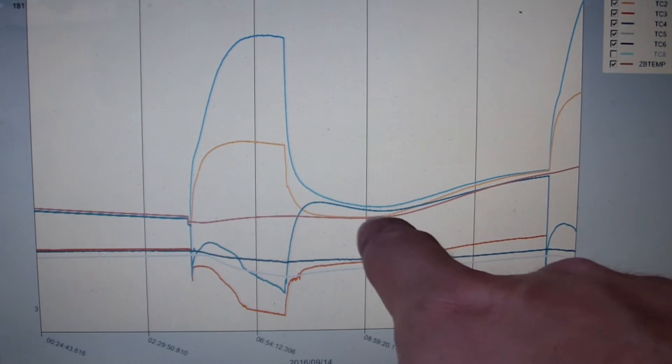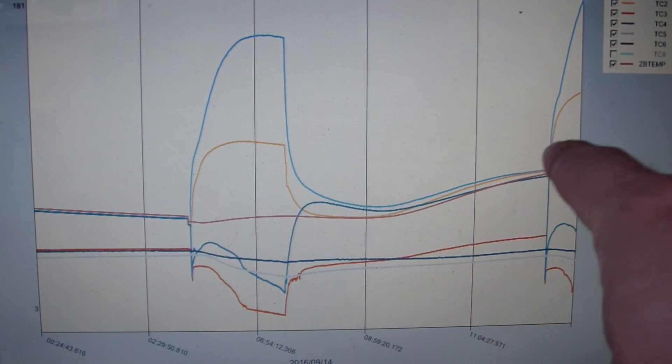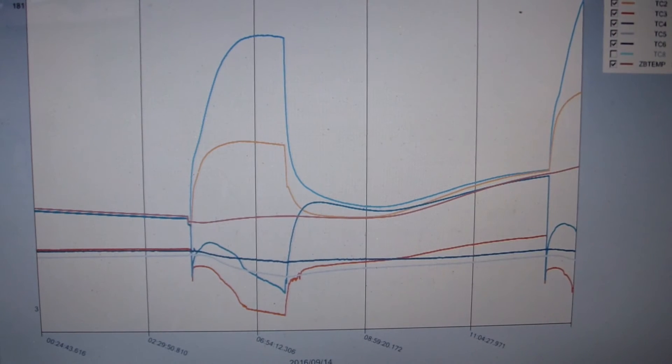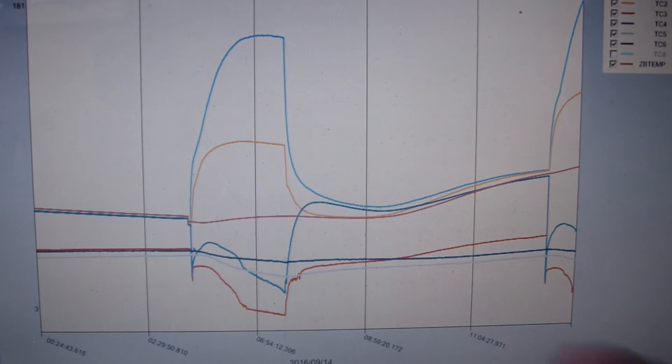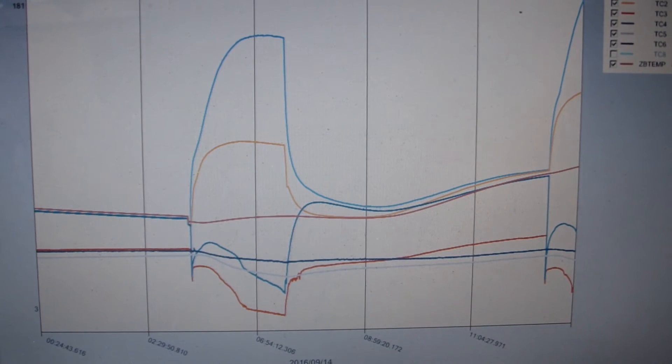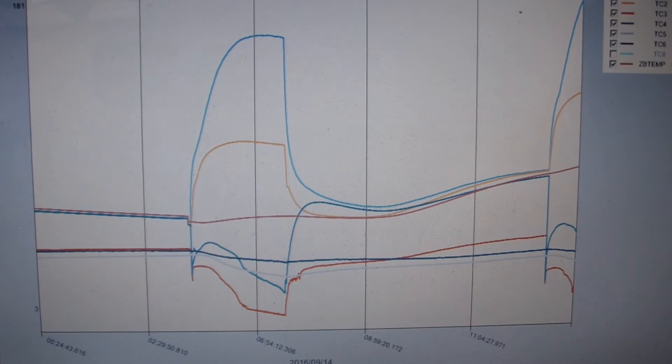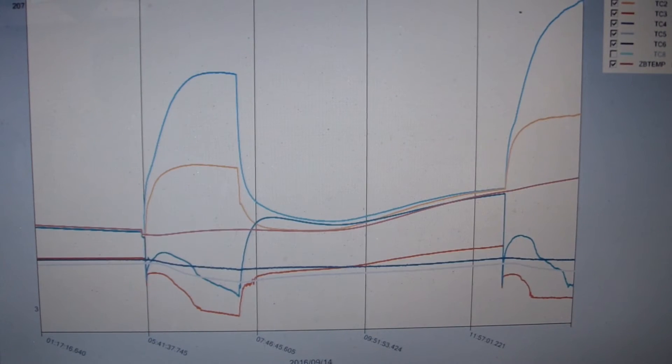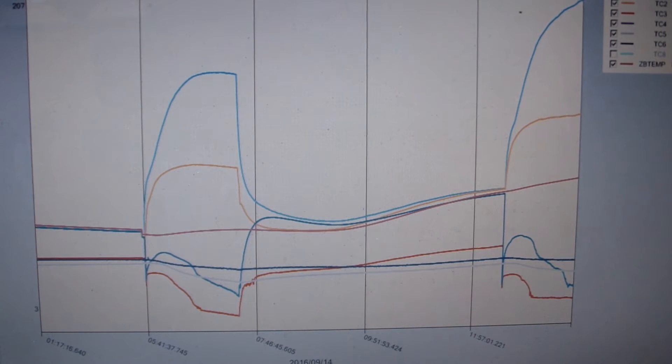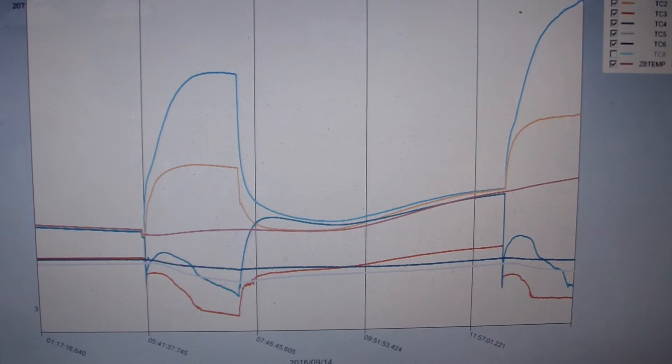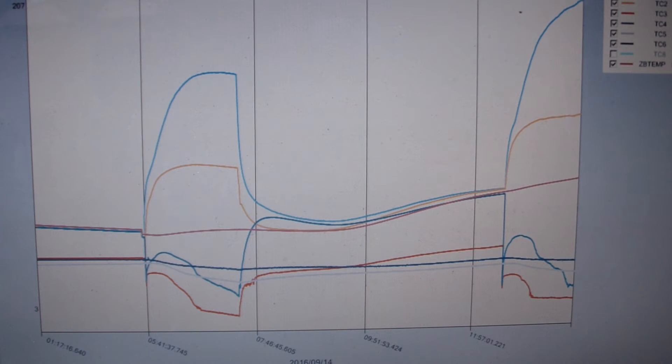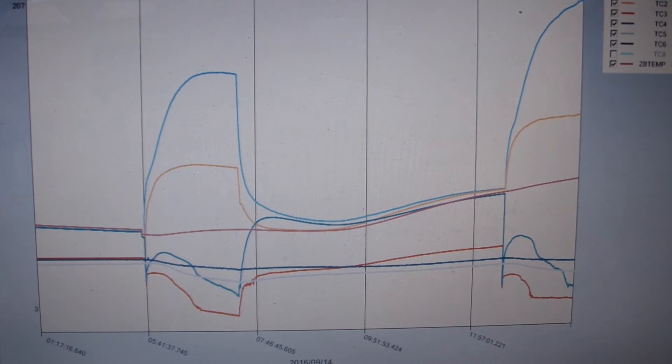See a very sharp rise in the ambient temperature starting about 9:30. It really started to go up. Even our superheat reading taken inside the box right after the evaporator started to rise pretty significantly. Now it's not very far from there, there's a hole that's probably not very well sealed from the air.